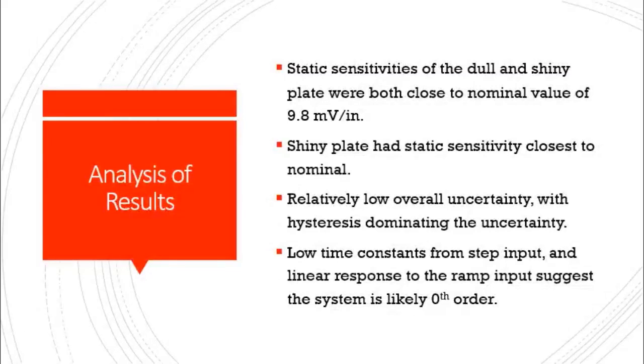We had a relatively low overall uncertainty, and hysteresis error dominated that uncertainty. Our combination of a very low time constant from the step input and a linear response of the ramp input suggested that the system behaves as a 0th order system.